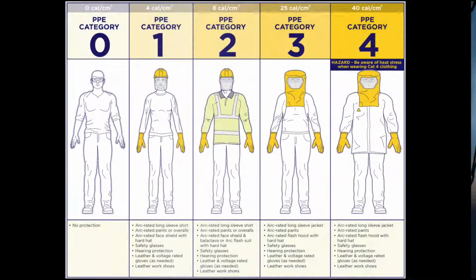So at 1.2, if I go back to my arc flash example, here we go. At 1.2, I'm really just wearing some modest protection: an arc-rated long sleeve shirt, pants, overalls, face shield, safety glasses, hearing protection, leather gloves, and leather shoes. Starting to sound like what you'd be wearing for COVID testing, but anyway, yeah, so that helps a lot.